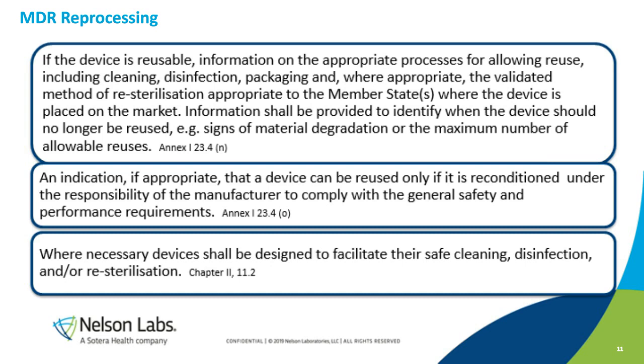Annex 1, Section 23.4, Section O states that an indication, if appropriate, that a medical device can be reused only if it is reconditioned under the responsibility of the manufacturer to comply with the general safety and performance requirements. Chapter 2, Section 11.2 states that where necessary, devices shall be designed to facilitate their safe cleaning, disinfection, and/or re-sterilization.